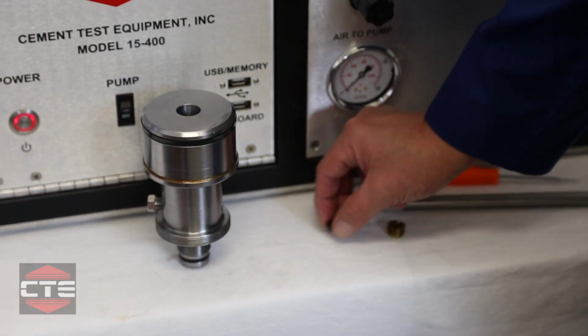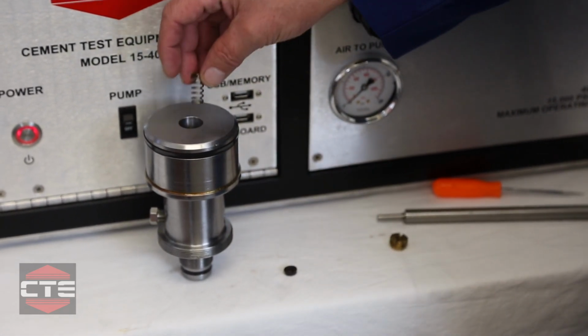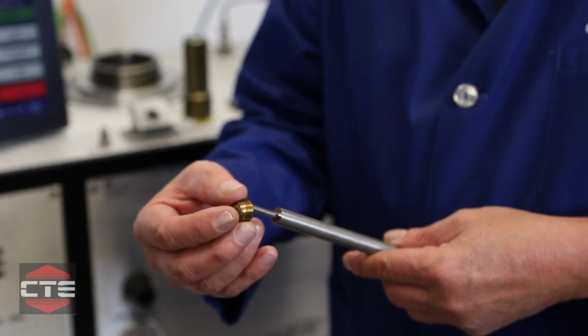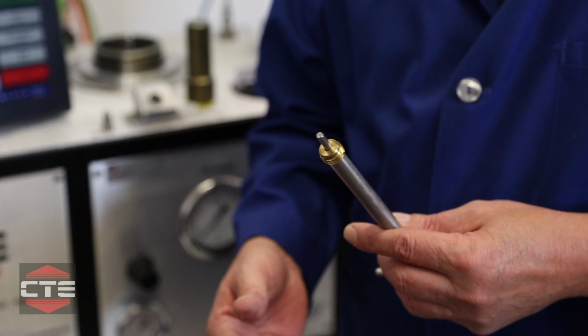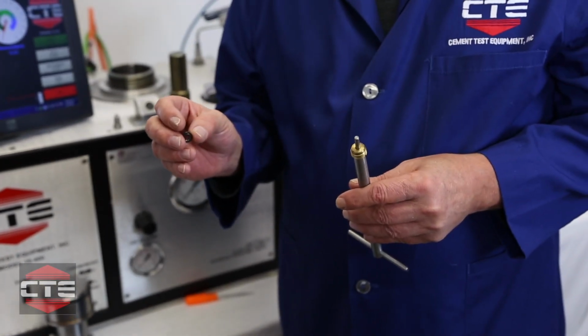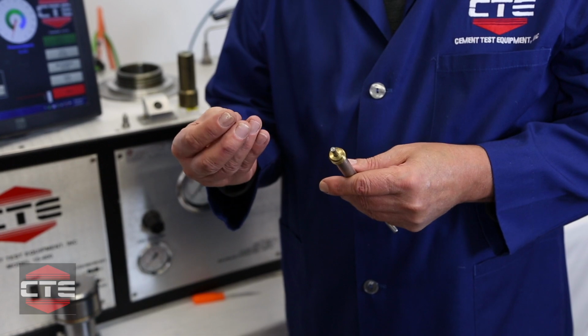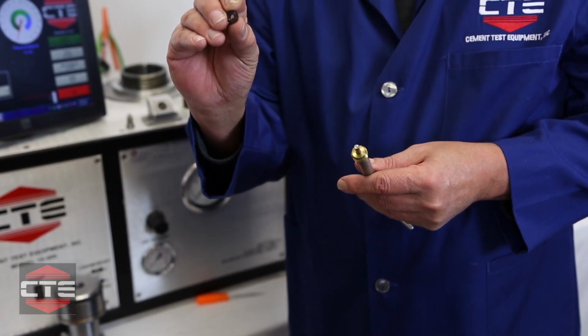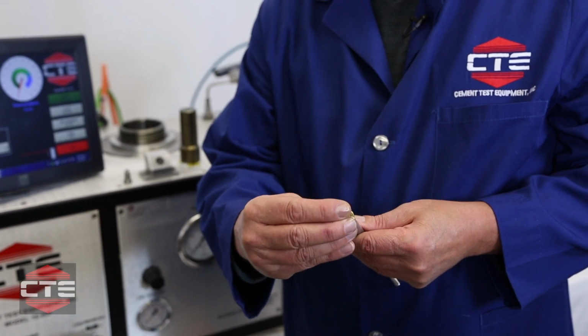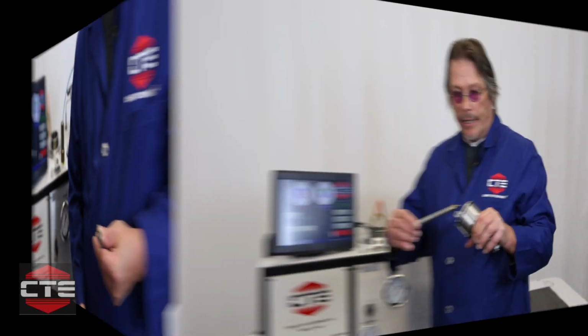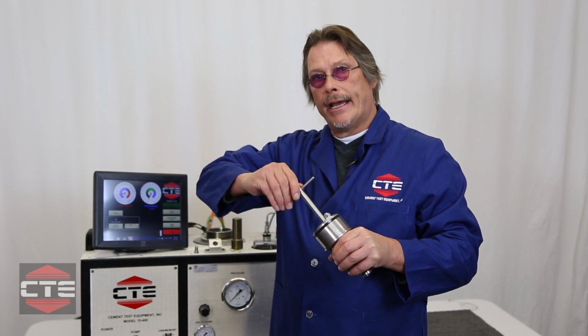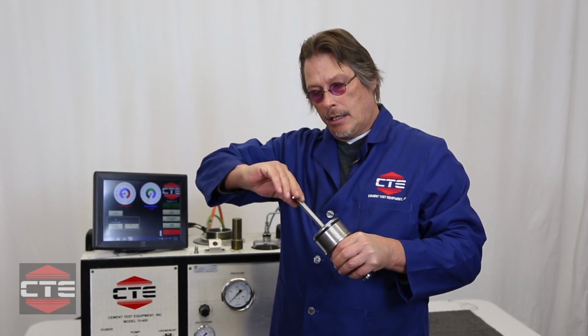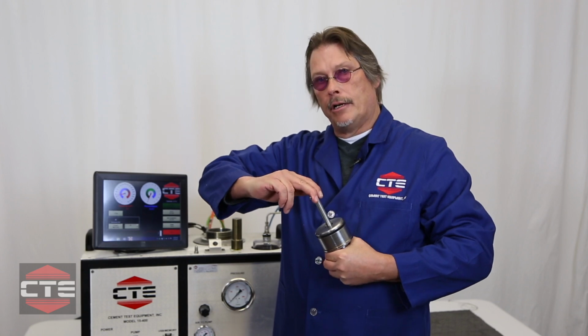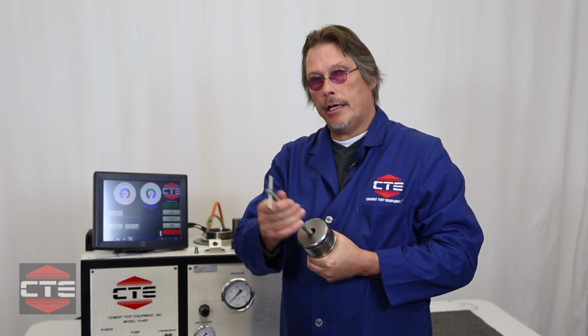So to reinstall your C-1066 poly pack, the first thing that goes in is your spring. It drops in. Visually verify that your spring is in place. Now we'll insert our seal retaining plug back onto our spring retaining tool. Now we will insert our C-1066 poly pack onto the spring retaining tool. And again, the brown insert of the poly pack, which faces pressure, will go against the bottom of the retaining plug. Now you will insert the spring retaining tool back into the head and screw clockwise until your plug bottoms out. This does not have to be done Herculean tight, just good and snug, and remove the tool.